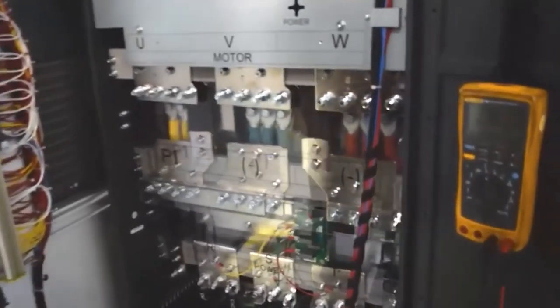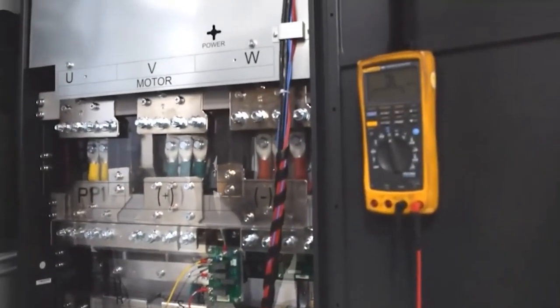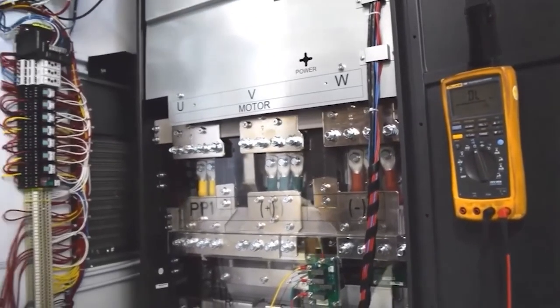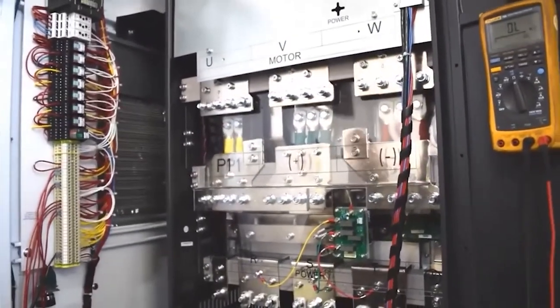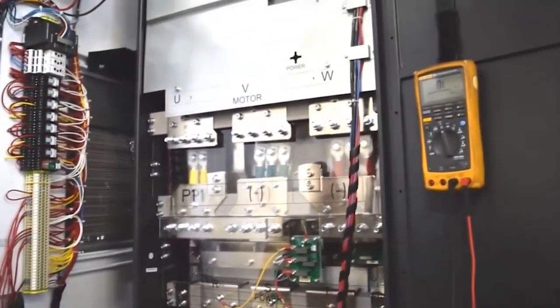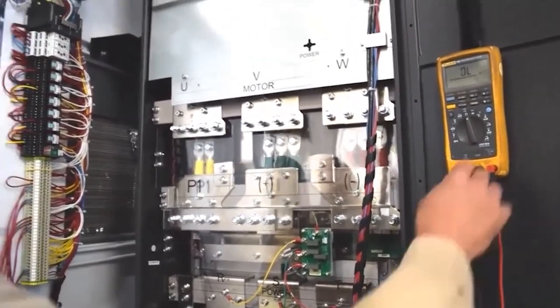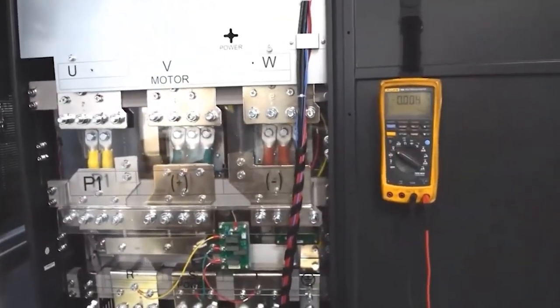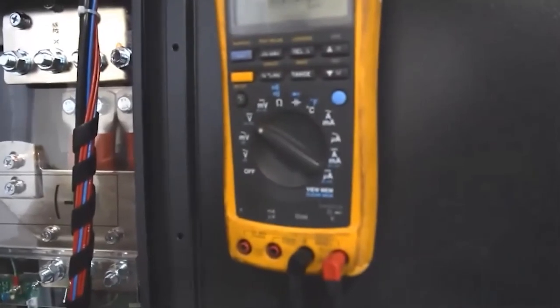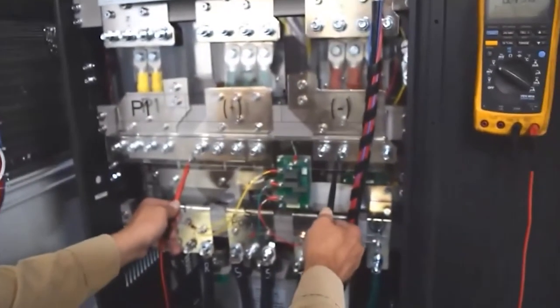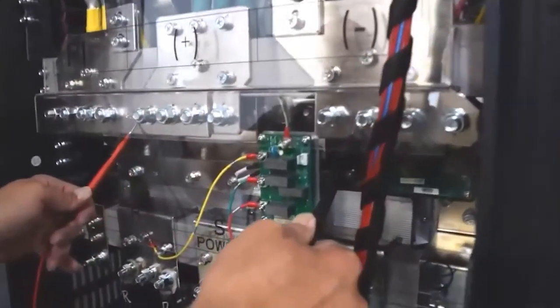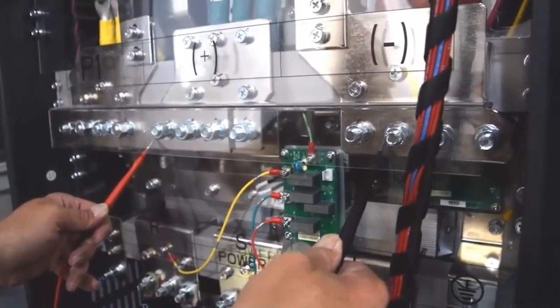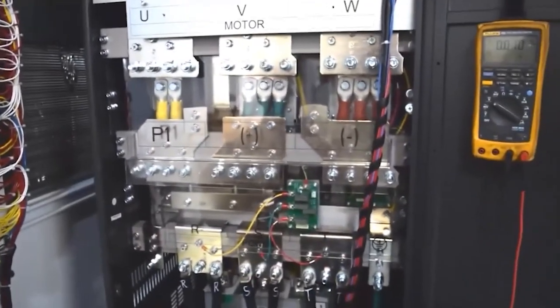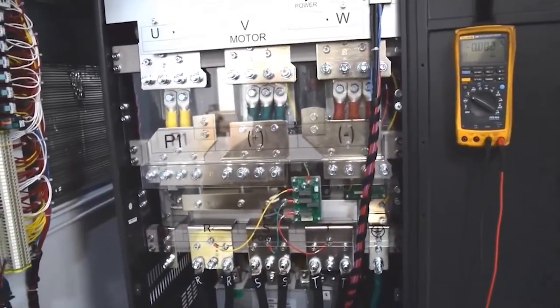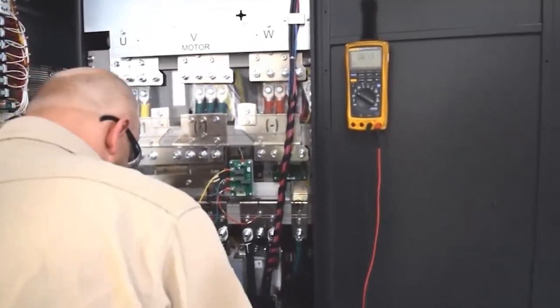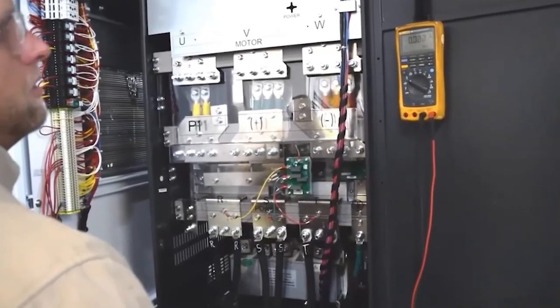So now that I've gone through and checked all the fusing out, everything's looking normal there, I'm going to go ahead and do a static check on the VFD, similar to what Craig was showing you. Anytime you get in a cabinet, the very first thing you want to do when you're doing any kind of static check is measure the DC bus. The DC bus can be charged for a long time, so I'm going to put my meter on DC volts. This has been off for a while, so I shouldn't have any voltage, but I always make sure, because if you have any more than about 7 or 8 volts, your readings are going to come back not right. So verify that your DC bus is completely discharged.